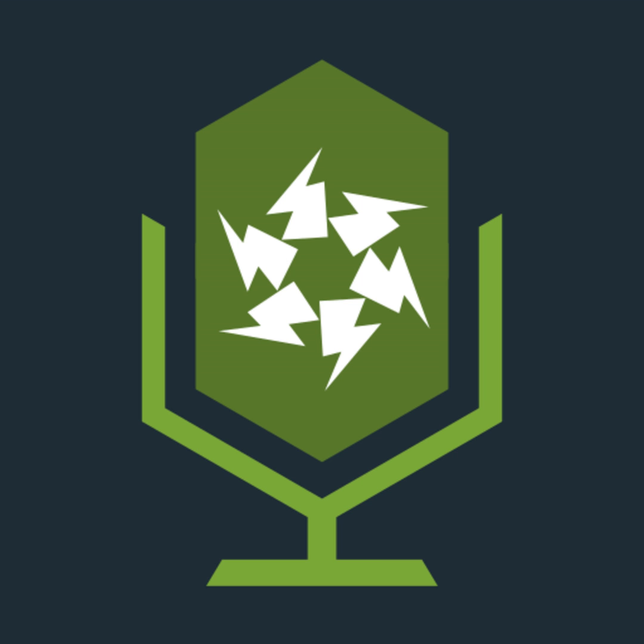We also have mentions on the erection of a wiring system, whether it be a strict type of wiring system or it could be overhead cabling, buried cabling. Now we mentioned a few videos ago about burying a cable only. There's no announced depth in BS 7671. It just says sufficient to avoid damage. But if you actually go to agricultural or horticultural, it will give you a depth. If you go to caravan parks, it will give you a height. So there are specified heights and depths through parts of special locations.